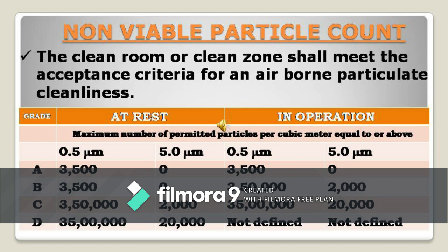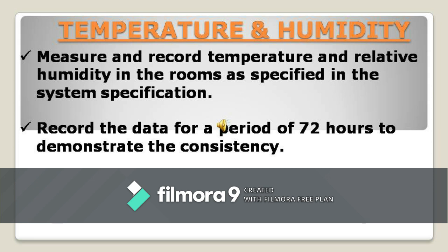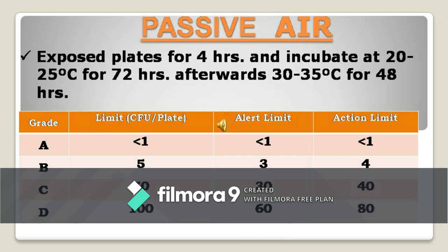Compare particle counts with the area range to confirm compliance. For microbial monitoring — passive air sampling — you need settle plates with SCDA media. Expose those plates at predefined locations determined on a rational basis by your microbiologist. Place them for at least four hours at those locations. Then incubate the SCDA plates at 20–25°C for 72 hours, followed by 30–35°C for 48 hours. These incubation conditions are the same for both active and passive sampling. Microbial growth limits after five days apply for grades A, B, C, and D.